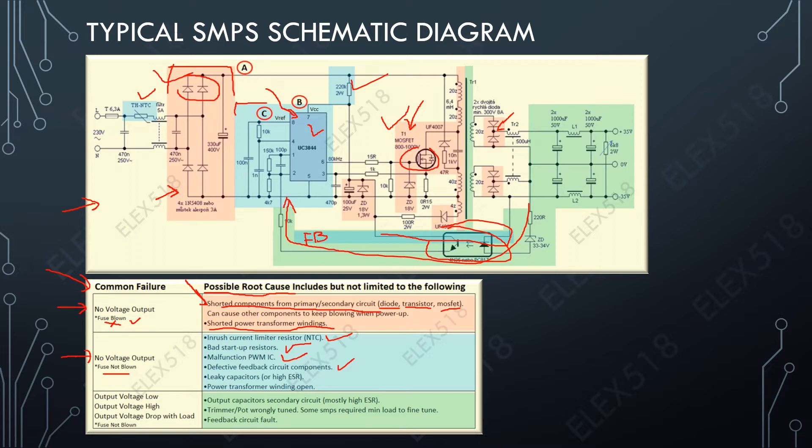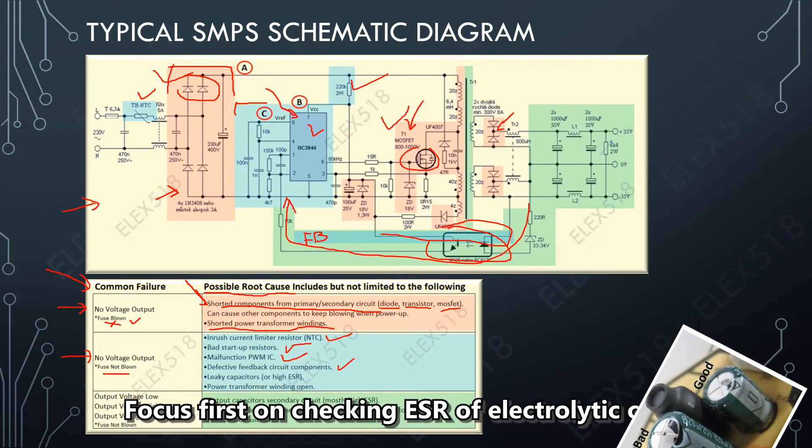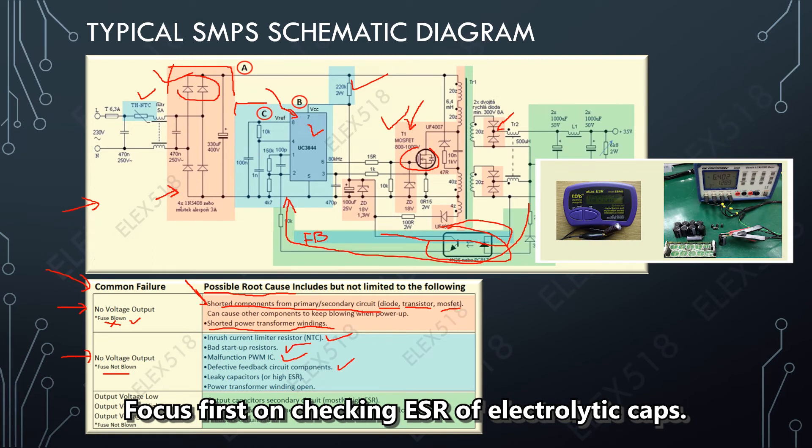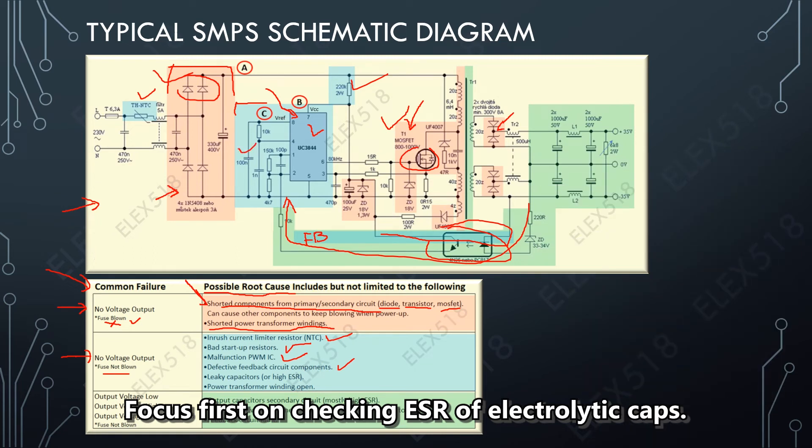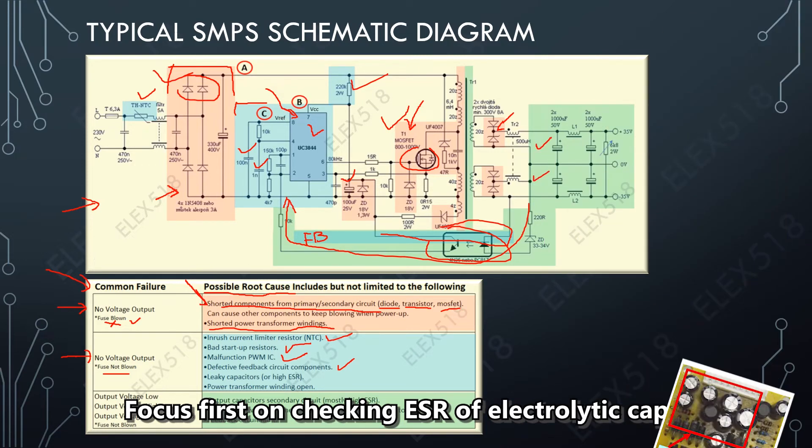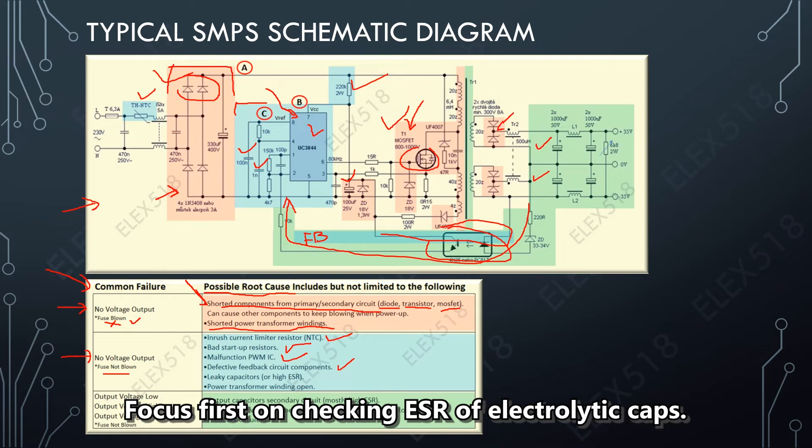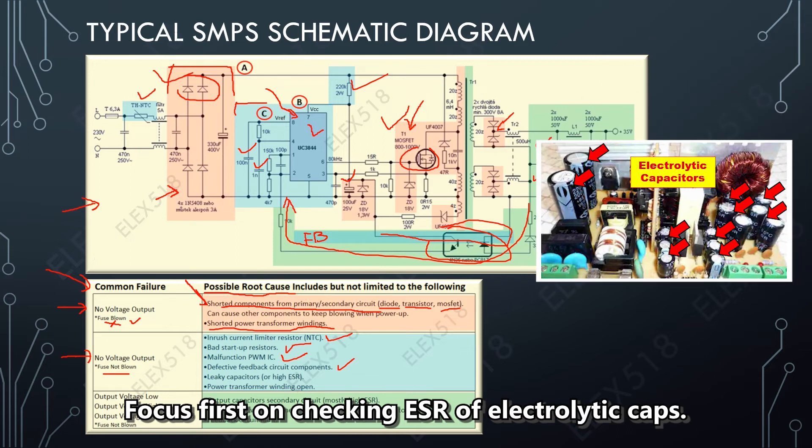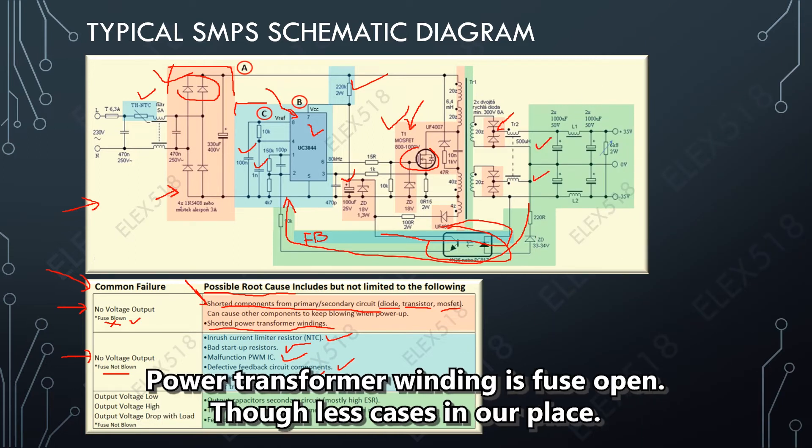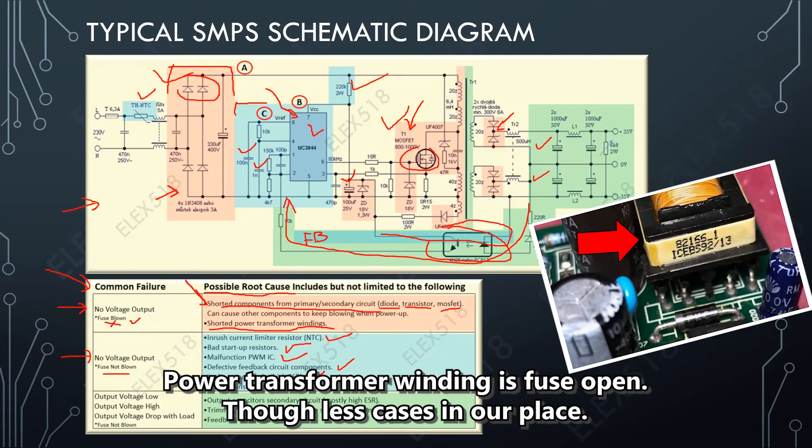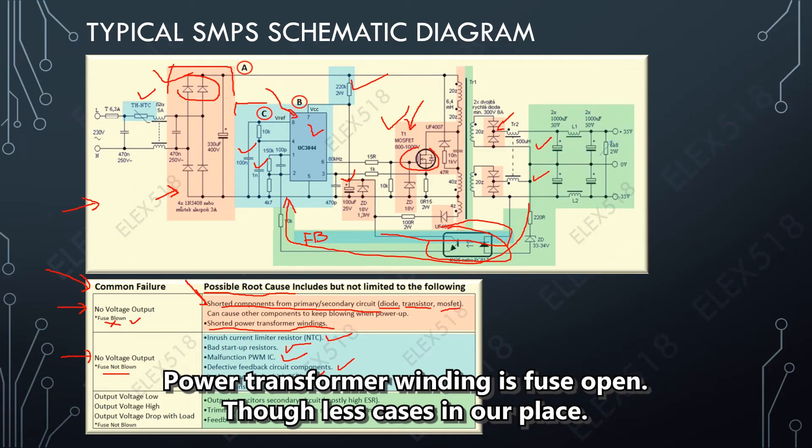Another potential root cause is leaky capacitor or high ESR capacitor. It could be these caps and also this output capacitor, but less likely. All the caps that have high ESR, especially electrolytic capacitors. The next one is power transformer winding open, and again it is very less likely to happen, but we also have experience that this power transformer winding was open and caused this type of failure.